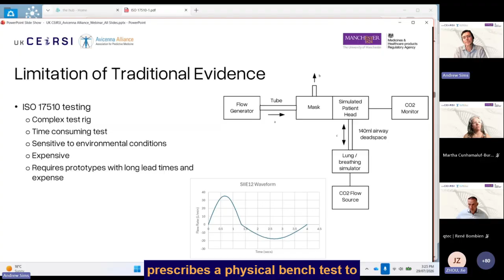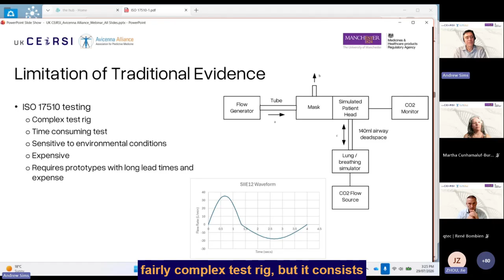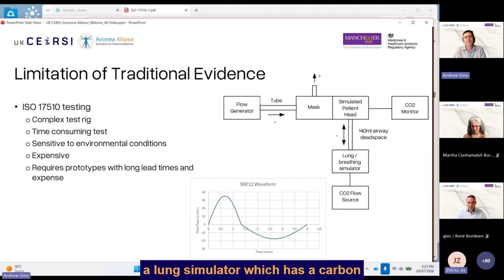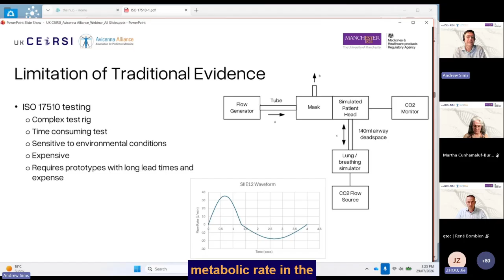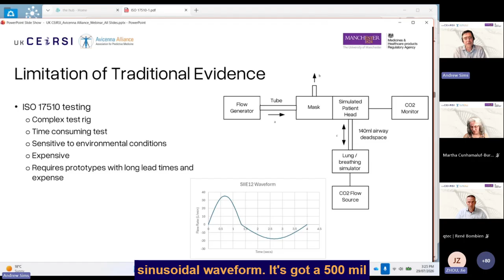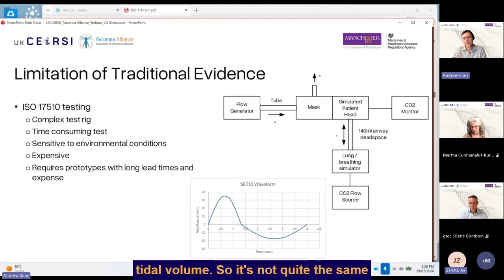ISO 17510 prescribes a physical bench test to demonstrate this. It's a fairly complex test rig, but it consists of a CPAP system. So we have our flow generator, a tube, and then a mask, which is attached to a simulated head. Along with this, we'd have something that would monitor the carbon dioxide, attached to a lung simulator, which has a carbon dioxide source that simulates a metabolic rate in the human. Along with that, there is a prescribed waveform, which is called a sinusoidal waveform. It's got a 500 mil tidal volume. So it's not quite the same as how we would breathe naturally, but this is the prescribed form in the bench test.